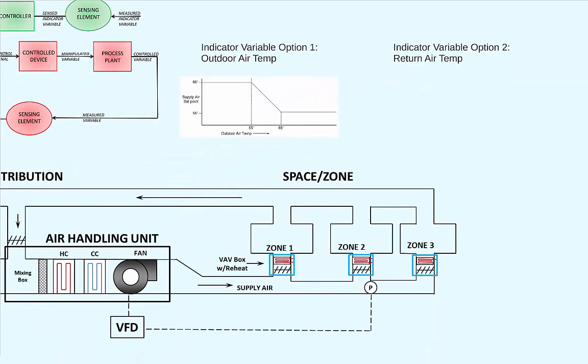So the new way of thinking is to reset supply air temperature based off of some other variable. That other variable would be that of the return air temperature. In this approach, we have a temperature sensor located in the common return duct. Say the cooling set point for all the zones is 74 degrees Fahrenheit.